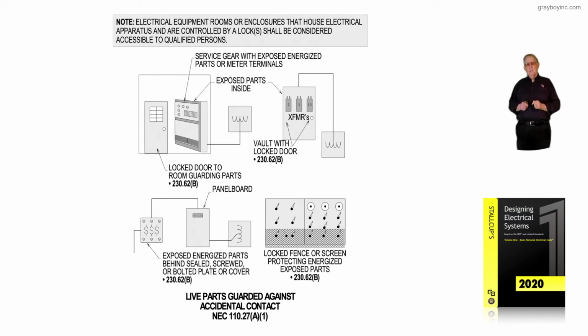Now this illustration deals with live parts guarded against accidental contact in accordance with NEC 110.27(A)(1). What this illustration is illustrating is when energized electrical components or conductors are in the exposed type condition.